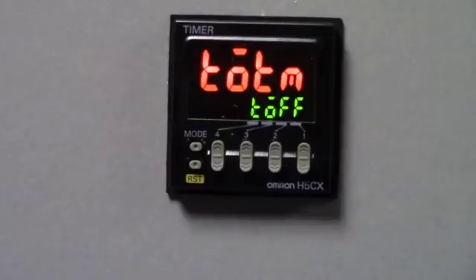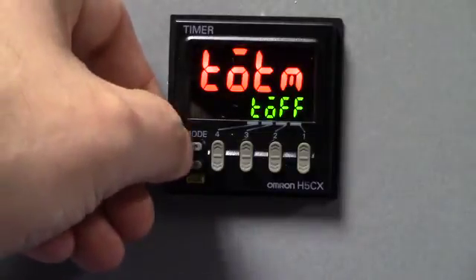Just to let you know, the other states available are flicker off start 1, a flicker on start 1, a flicker off start 2, a flicker on start 2. So depending on the application, you could determine the timing sequence of the timer. And for today's video, I'm just going to keep it with the factory default. This being the case, I'm going to press the mode key one more time.